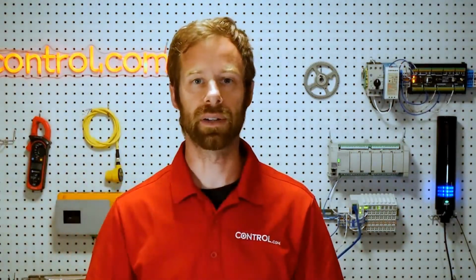Each one of these wires is able to be connected to what's known as nodes, not sensors. This one again does not directly connect to the sensors, but it connects to the nodes. And these nodes usually contain a couple of M12 plugs that you can connect the sensors to. Depending on the version of ASI you've got, some evolutions have taken place, with ASI version 3 being capable of 4 bits per node, which is great for 4 pieces of data, and it can be output or input data. So you might see a node that clamps right on top of the cable with 4 M12 connectors, one for each sensor or perhaps a relay or a contactor.